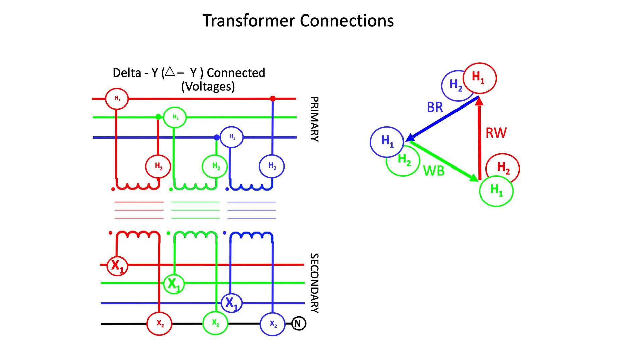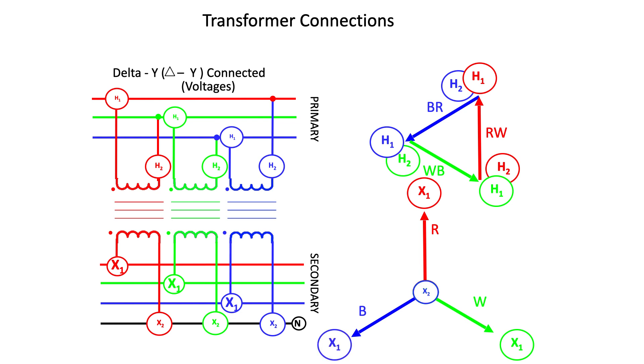You'll notice that the X2 terminals are jumpered to the X1 terminal of the adjacent phase, forming that recognizable Delta connection. On the secondary side, you have the red, white, and blue phases. The X1 to X2 of the red phase are shown, then the white phase, with the X2 of the white phase connected to the X2 of the red phase. The X2 of the blue phase connects to the X2 of the white and red phases — because they are all connected together, the X2 terminals form a neutral on the secondary side.